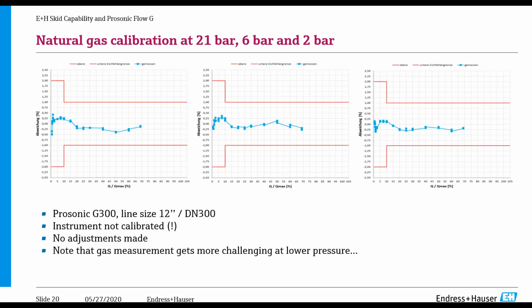So these are the results. From left to right, we're starting off with 21 bar, higher pressure, and we're well within our specification. Then 6 bar. As pressure decreases, this has always been a challenge for ultrasonic meters, so normally some of them would stop working at certain pressures. We are actually able with our meter to measure down even into slight vacuum conditions. So you can see as we move left to right, we're decreasing the pressure, but we're still maintaining our accuracy with this meter. And just to repeat, this meter was not calibrated, so there was no flow calibration or linearization done on it before it went out.